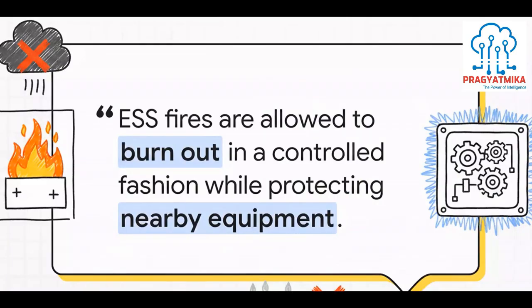Today, the current industry best practice combines explosion prevention with fire containment. The idea is that fires are allowed to burn out in a controlled fashion while protecting nearby equipment. In many scenarios, if a fire starts inside an enclosure, it's intentionally allowed to burn out completely safely—letting those flammable gases combust as they're generated totally avoids the risk of a sudden, catastrophic explosion.